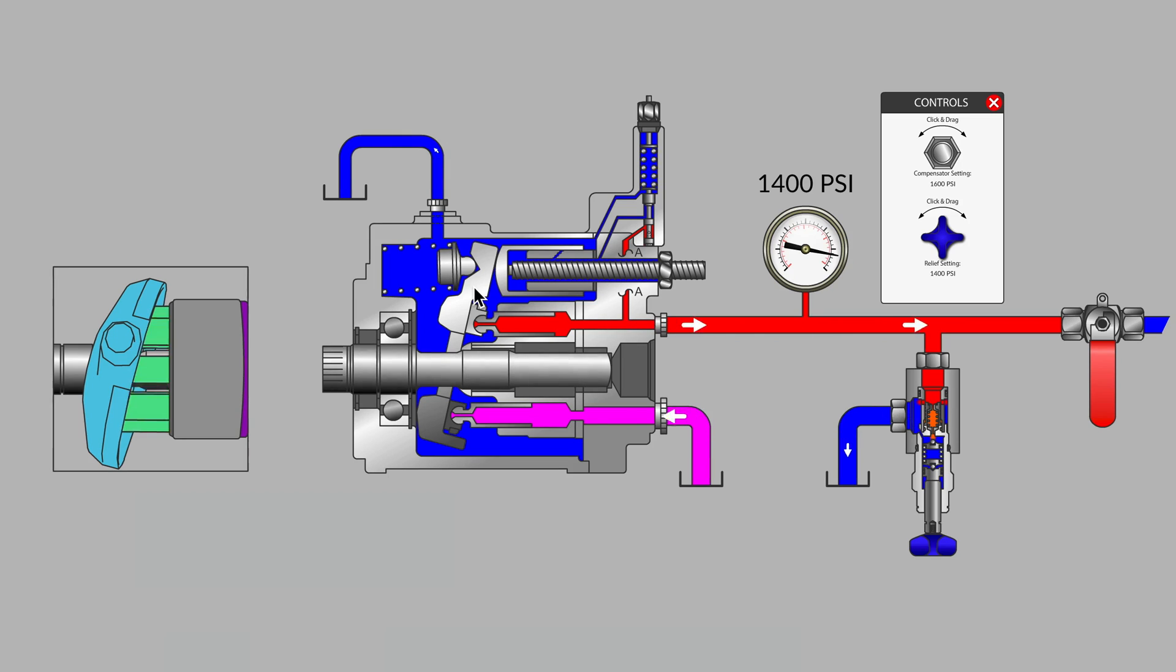When this occurs, the pump will be set in a near-zero displacement mode. The pump, together with its pressure compensator, will be able to hold the maximum safe system pressure while producing very little flow.